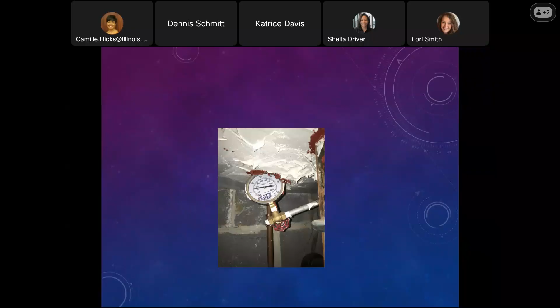This is actually from an Illinois facility. There was a fire in the facility. The sprinkler heads in the room where the fire was did not discharge, so they had to do an internal investigation. Why did the fire not get put out by the sprinkler system? This is an internal investigation of the sprinkler system, which is required every so many years on wet systems.